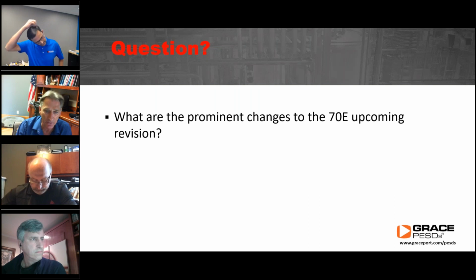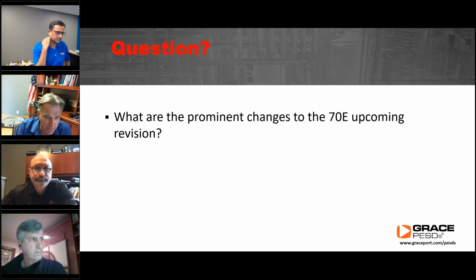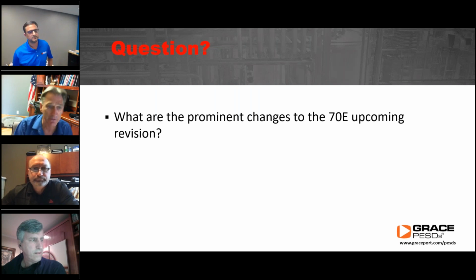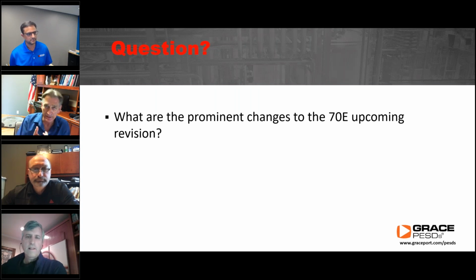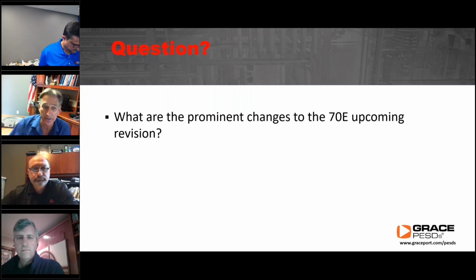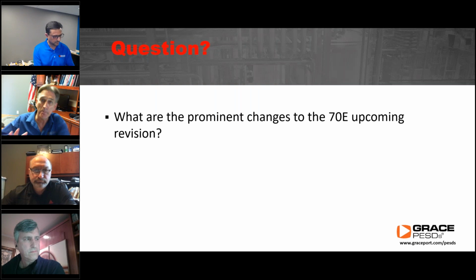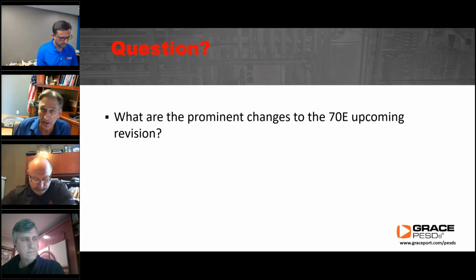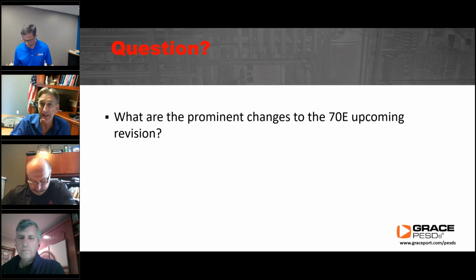One of the things that was - and this will be the last one I'll talk about here, we'll save the rest for another webinar - is in 130, talking about outer layers, in section 130.7C9B. In that section right now it says garments worn as outer layers over arc rated clothing, such as jackets, high visibility apparel, or rainwear, shall also be made from arc rated material. That's in there now. What I have always been teaching was that outer layer had to be equal to or greater than the potential incident energy.